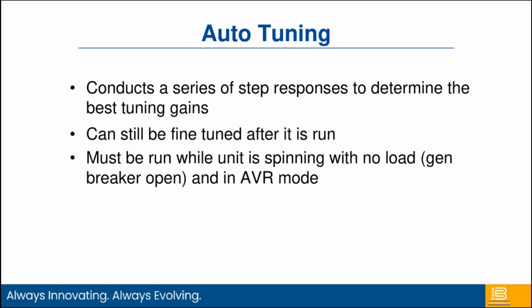Maybe it's too aggressive for our operators. Depending on the machine, they may not want a very aggressive response. If I've got a lot of dynamic loads, I may want a very fast response that I can recover from very quickly. So I may want almost, bordering unstable, where I get as fast a response as I can. So I can come back and retune and use those as my base settings to get me close. And now I'm just making little tweaks and not spending hours trying to get the right gain settings.